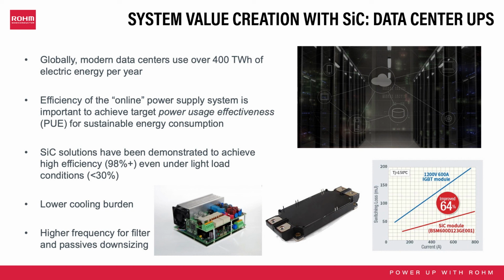With silicon carbide, we can substantially cut the energy waste of the UPS, especially in light load conditions, improving the data center's power usage effectiveness and reducing the cooling burden, besides the possibility to also downsize the power supply system.